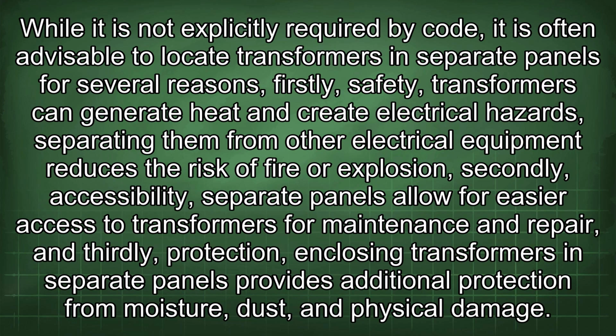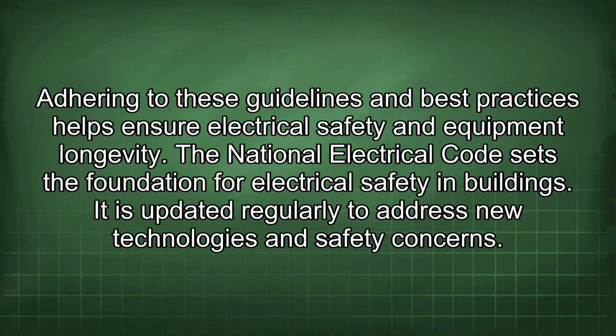While it is not explicitly required by code, it is often advisable to locate transformers in separate panels for several reasons. Firstly, safety. Transformers can generate heat and create electrical hazards. Separating them from other electrical equipment reduces the risk of fire or explosion. Secondly, accessibility. Separate panels allow for easier access to transformers for maintenance and repair. And thirdly, protection. Enclosing transformers in separate panels provides additional protection from moisture, dust, and physical damage. Adhering to these guidelines and best practices helps ensure electrical safety and equipment longevity.